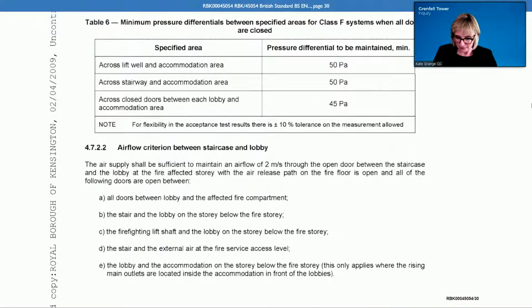The question you're putting to me is as though I would have to accept what you say is correct. But I believe the SCA guide cites this as an acceptable standard for the damper. We could go to it if you wish. Well, do you know where it is in the SCA guide? Well, not off the top of my head, but it must be near the area where you were just now. I'm just putting to you that if it's going to be a smoke control damper, which it needed to be, there needed to be relevant test evidence to BS EN 1366 Part 10 and classification to BS EN 13501 Part 4. And the dampers didn't demonstrate that.